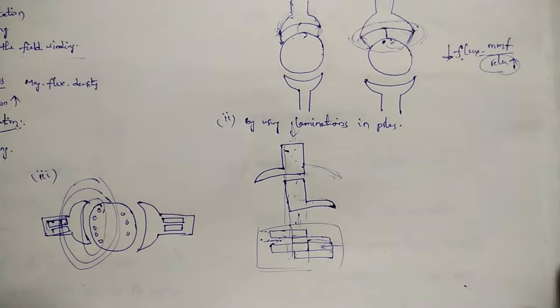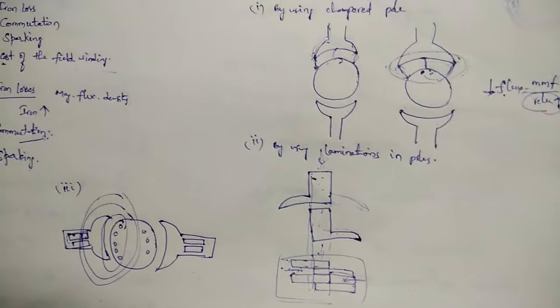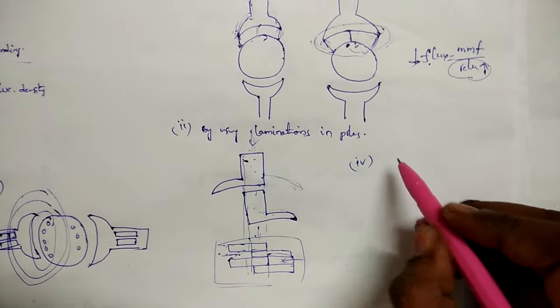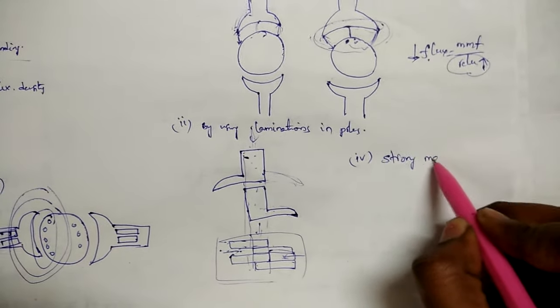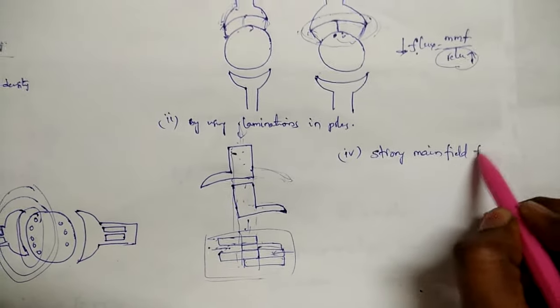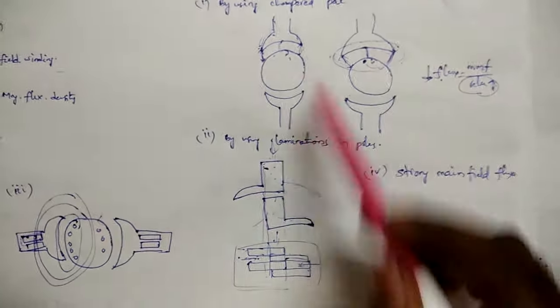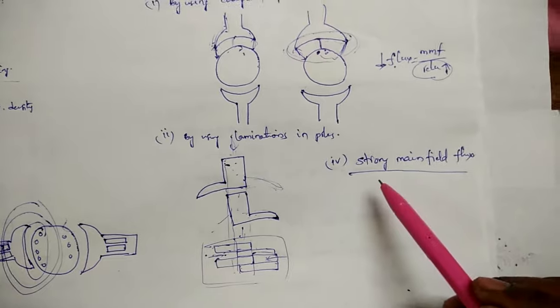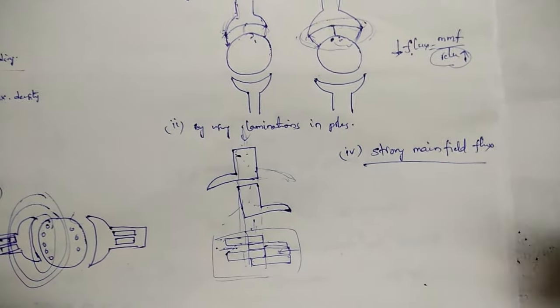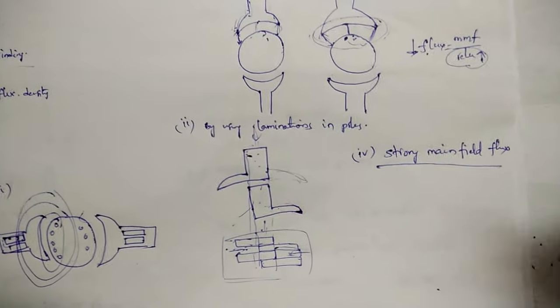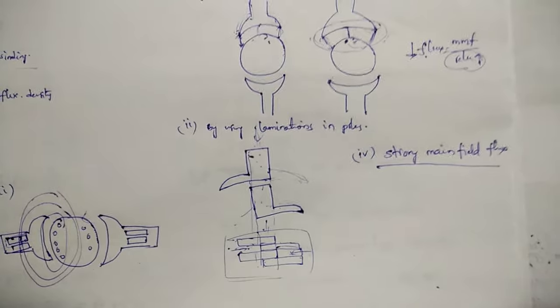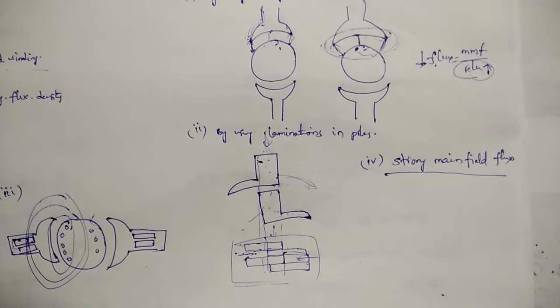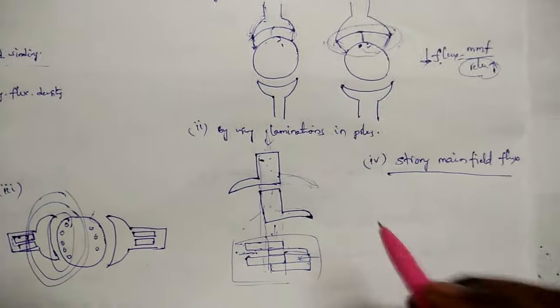The fourth method is by making the main field flux strong. While the first three methods reduce the armature flux, this method increases the main field flux during the manufacturing process by winding more number of turns in the main field winding. With a stronger main field flux, the armature flux cannot influence it as much, even under heavy loads.